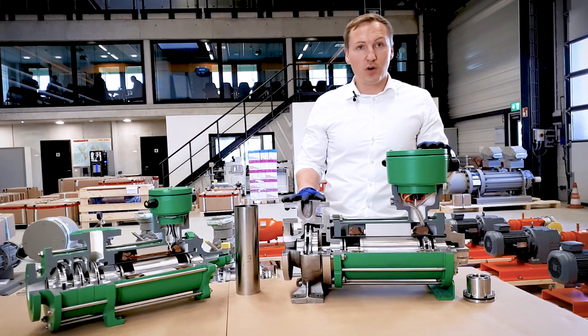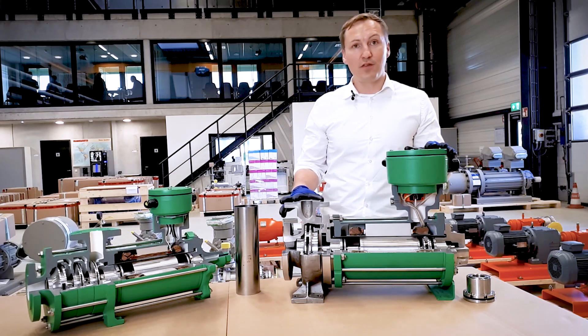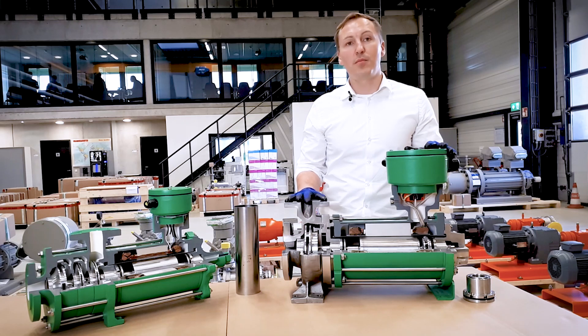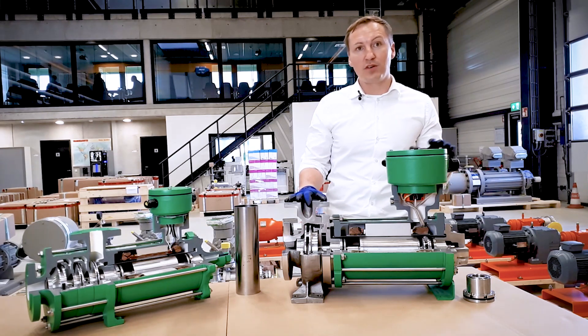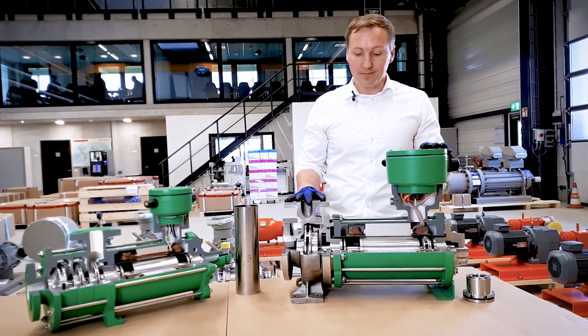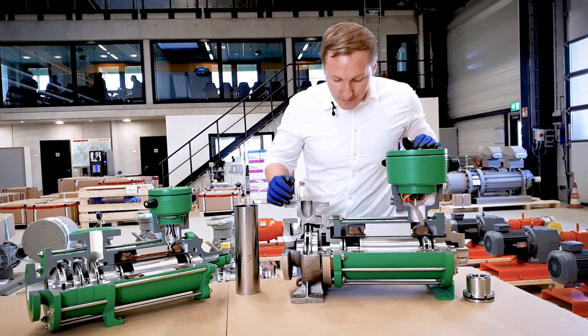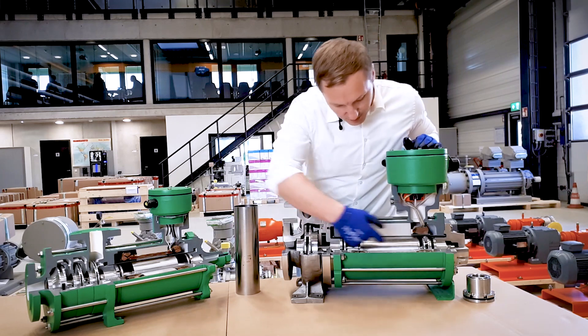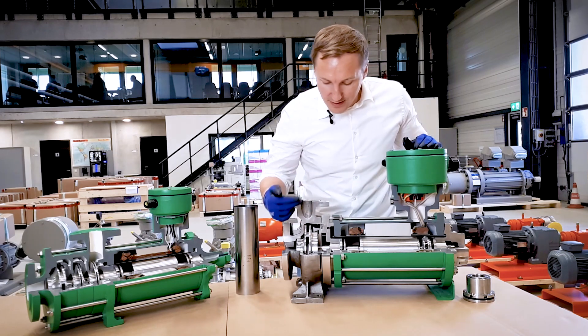This is a Canned Motor Pump — a very unique and compact design, which means we integrate the motor into the pump. That means no external parts like a separate electric motor, and that means we have a sealless technology. We integrate the motor by mounting it to a hollow shaft. What you see here is the hollow shaft, and mounted on this hollow shaft is the impeller.